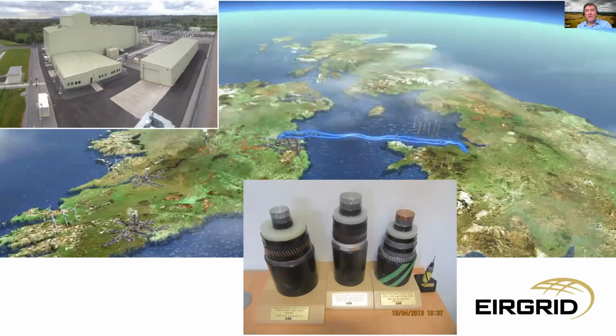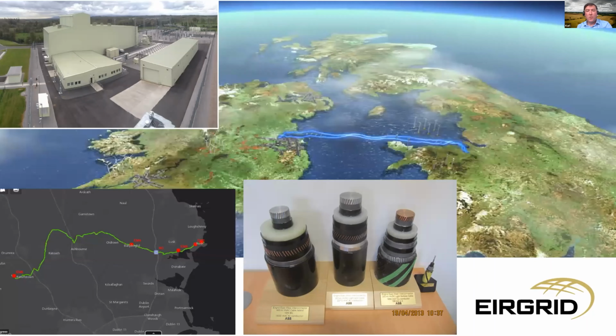The EWIC HVDC cables are rated at ±200 kV, and they total 265 kilometers end to end: 44.5 kilometers in Ireland on land, 186 kilometers of marine, and 34 kilometers in Wales. The cables are cross-linked polyethylene, XLPE, and are made of copper and aluminium, as you can see there, these 2 cables. To connect to the transmission systems, there's 5 kilometers of 400 kV AC cable in Wales and 0.5 kilometers of 400 kV AC cable in Ireland. That's the AC cable there.